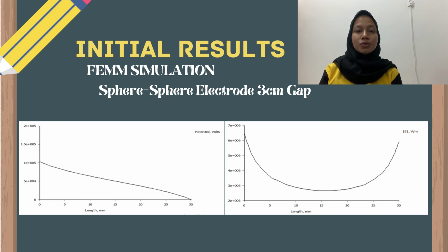The figure on the left side shows the graph of potential V versus gap length for both sphere and sphere electrodes. By referring to the figure again, the voltage is decreasing from A to B, and the bottom electrode does not have much voltage. From the figure on the right side, the minimum electric field occurs in the middle of the gap, around 2.7 megavolt per centimeter, and the maximum electric field occurs at points A and B, which is 6.5 megavolt per centimeter. In conclusion, the longer the gap length, the lower the electric field intensity between the electrodes, which makes it harder to break down.